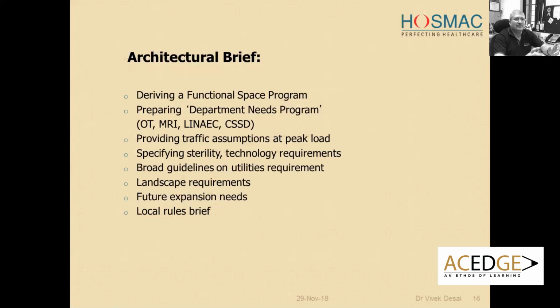In an operation theater, there are minimum sizes given by certain norms. 400 square feet is the operation theater minimum. Also, it should generally be square and not a rectangle, because otherwise it will create air turbulence, since it needs a particular type of air conditioning for the operation theater.